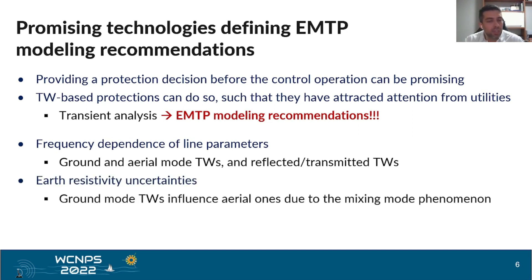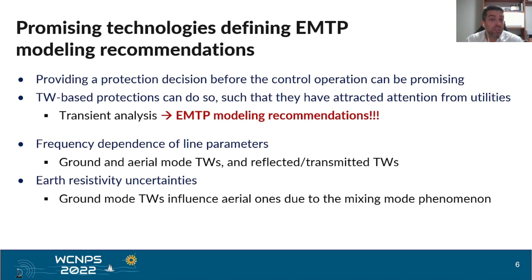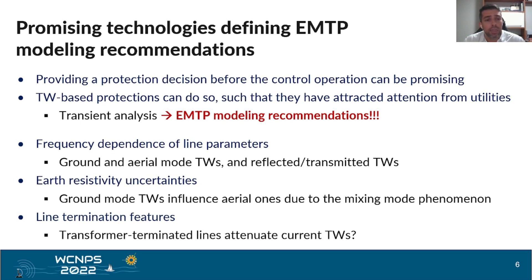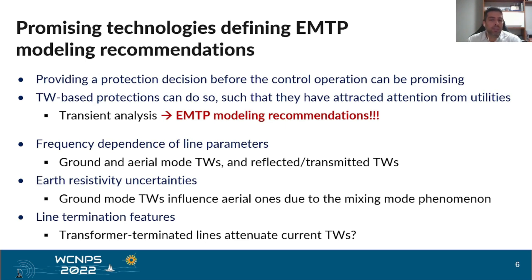Earth resistivity uncertainties must also be considered, such that the soil must be accurately modeled if possible, because ground mode traveling waves influence aerial ones due to the mixing mode phenomena. Also, the line termination features must be considered, because the connection lines of IBRs are usually terminated by transformers that attenuate current traveling waves. In this case, the stray capacitances over the transformer and at the bus bar must be represented.